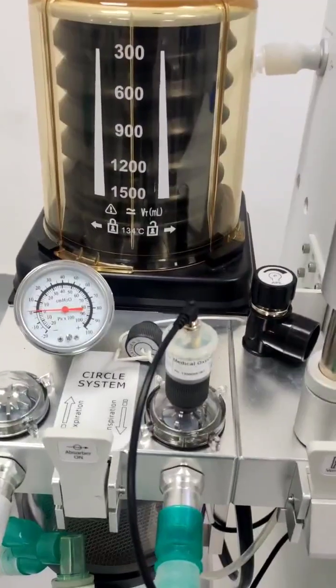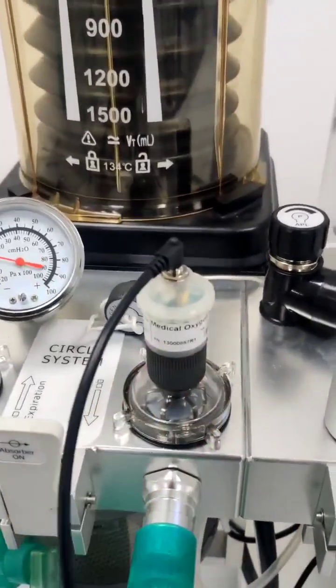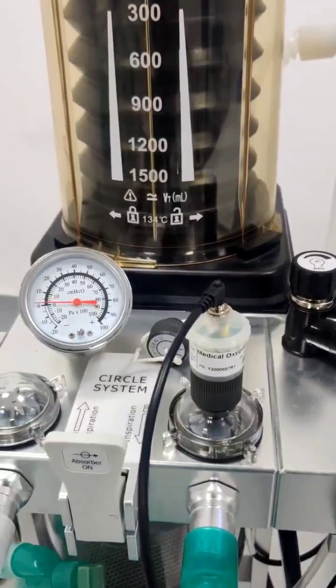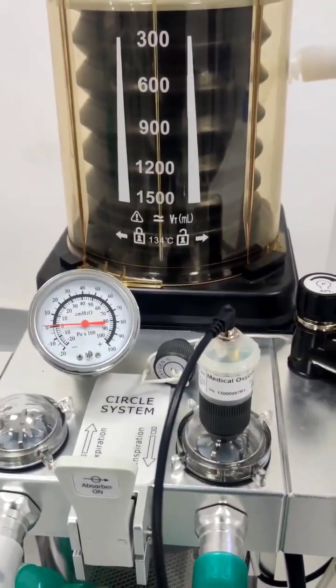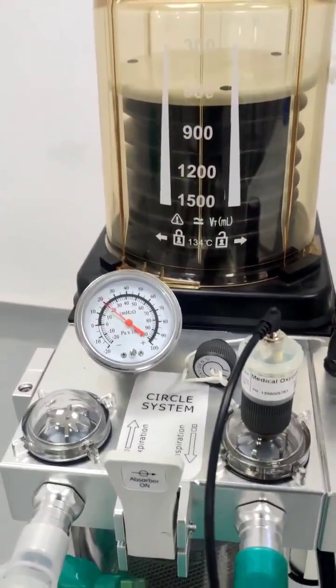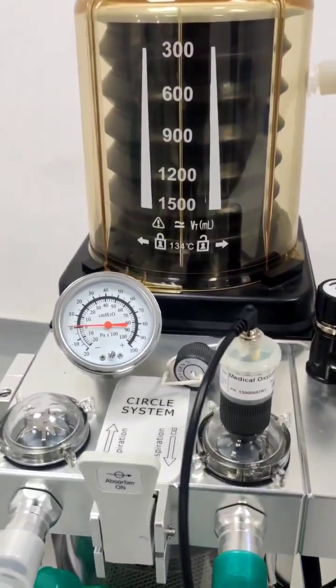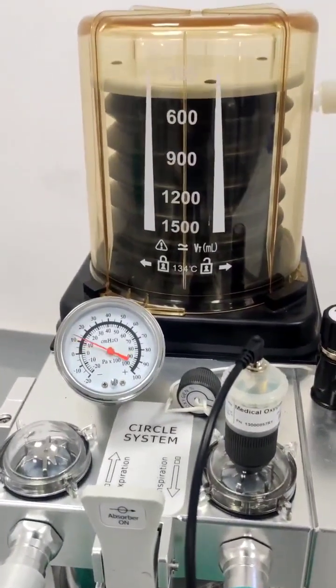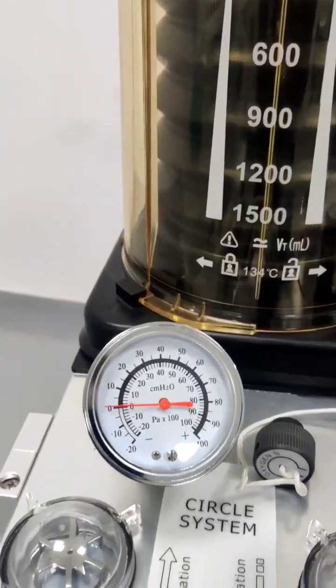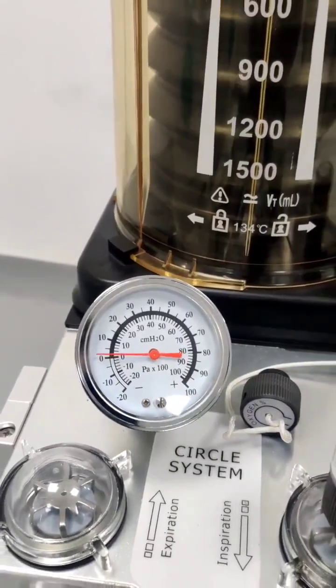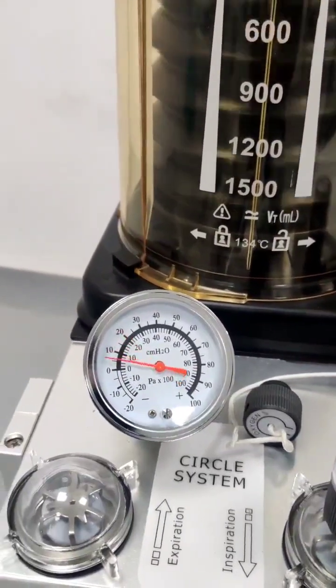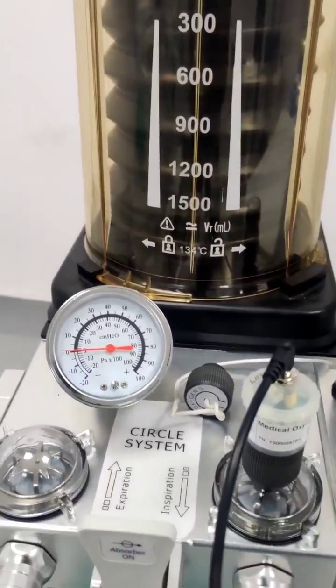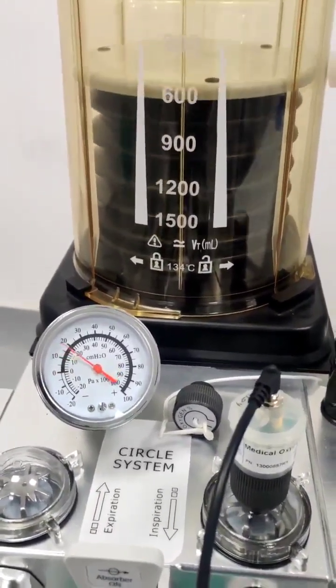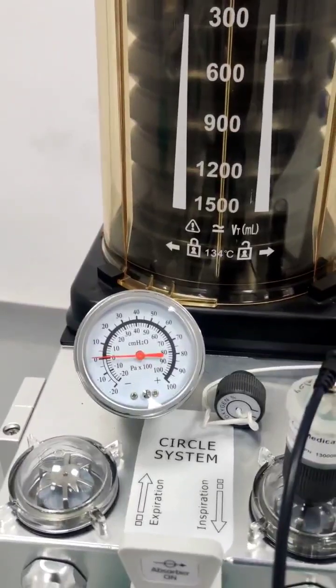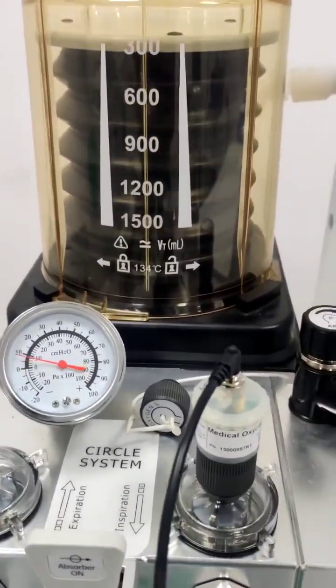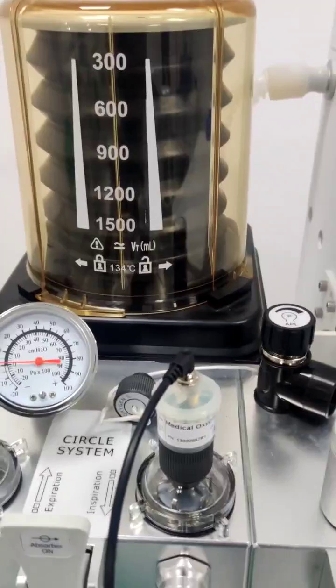On the circle absorber side only, we are giving the oxygen sensor, which will give you the FiO2 value, that is the amount of oxygen delivered to the patient. This is the sensor which measures the amount of oxygen being delivered to the patient. And we are giving the manual manometer over here to measure the airway pressure of the patient. Though we also get the digital pressure on the ventilator screen, this manual manometer will give the airway pressure of the patient.